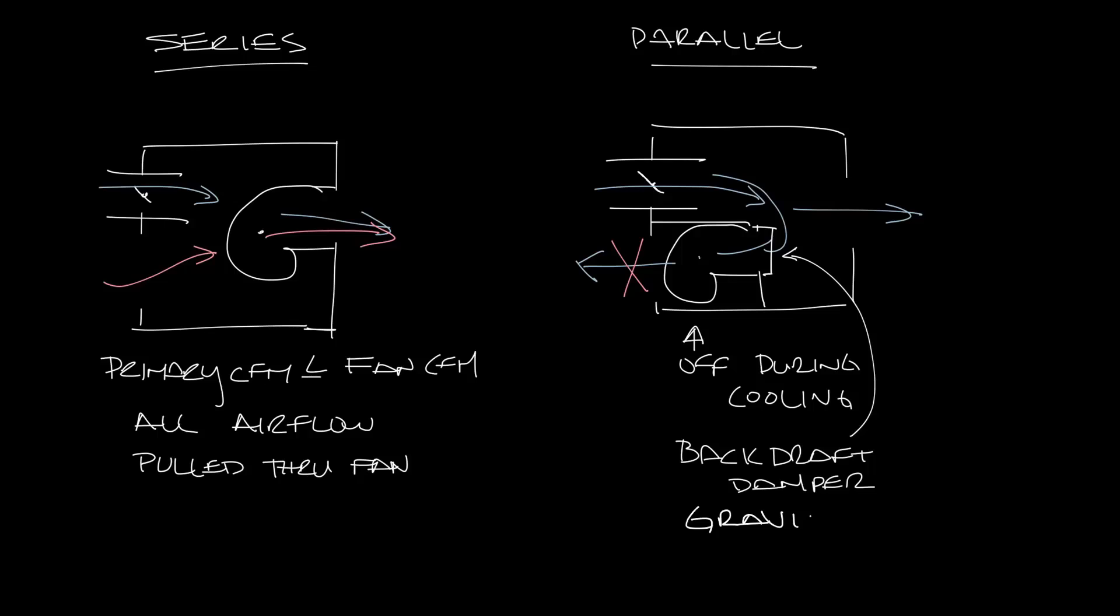This is usually a gravity operated damper. So it just hangs down in front of the fan while the fan is off. And then when the fan is turned on, the airflow from the fan pushes the damper open and allows the induced air to mix with the supply air.